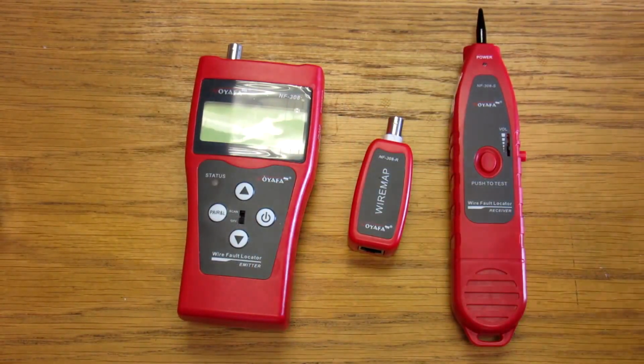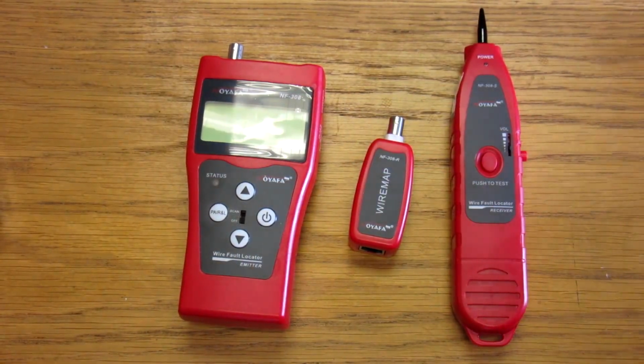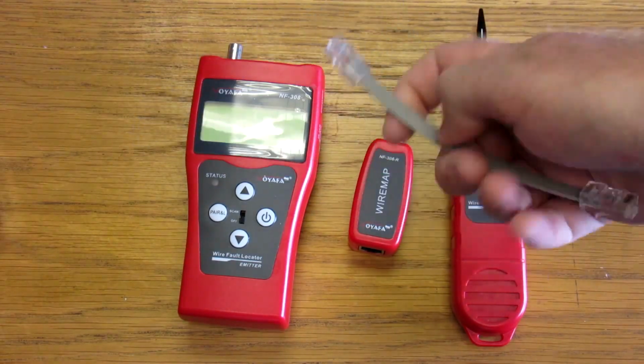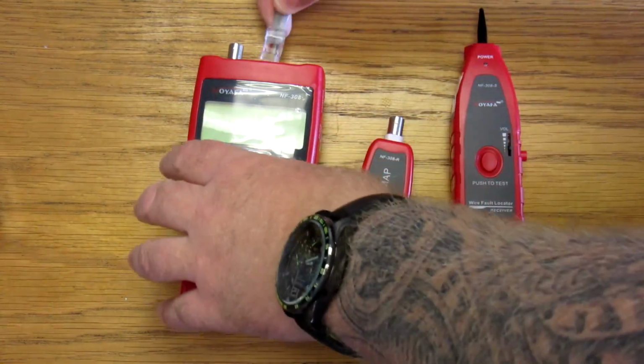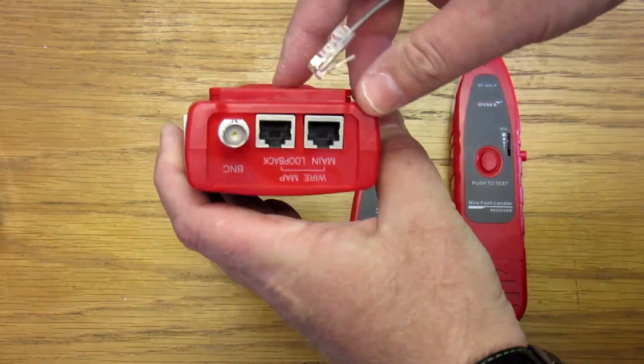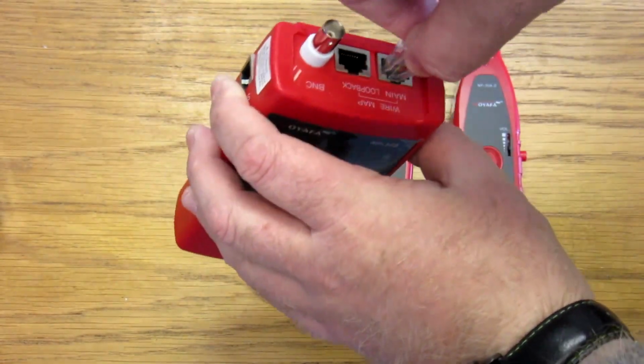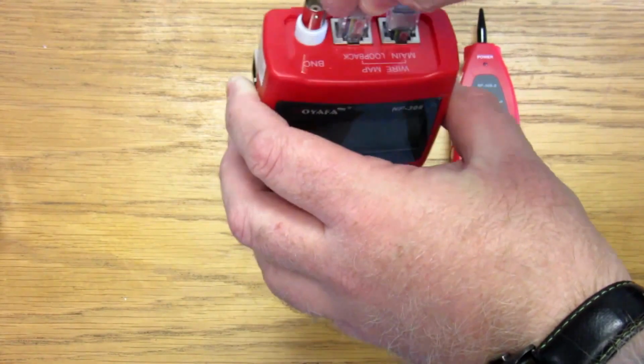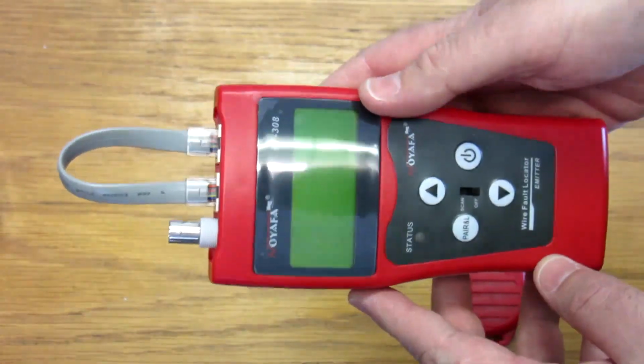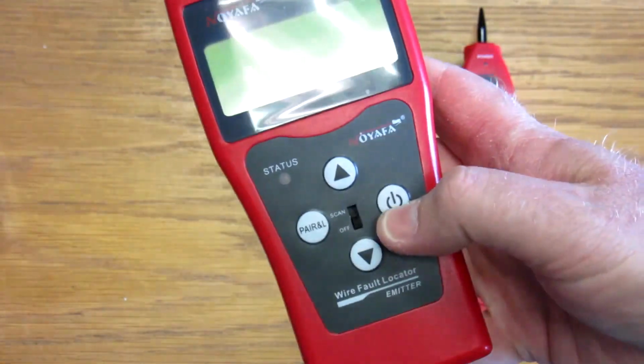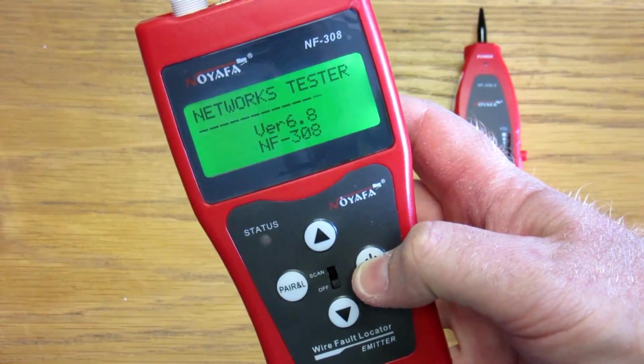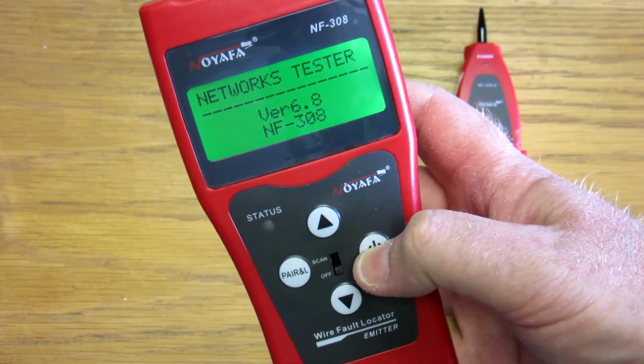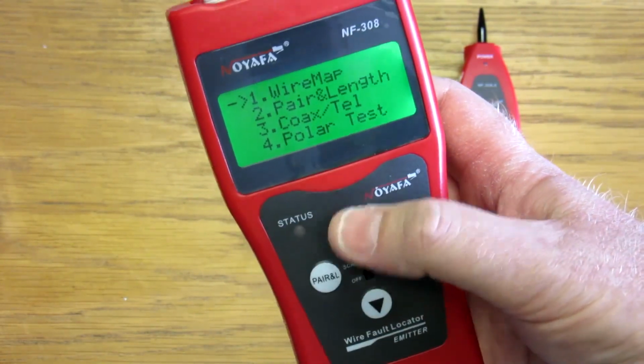Okay, first step is a standard cable test. What we're going to do is test this little piece of cable, which is one of the test cables that comes with it. To do this, we come to the top of the unit, plug in onto main, and we can plug into loop back if we want to just test a small piece of cable. Then we switch the unit on, and then you see you have wire map.